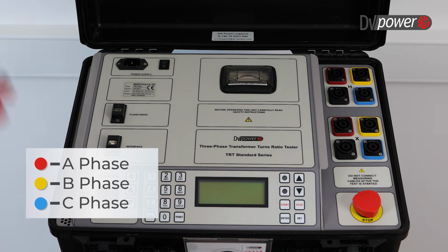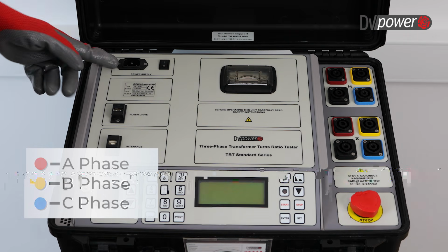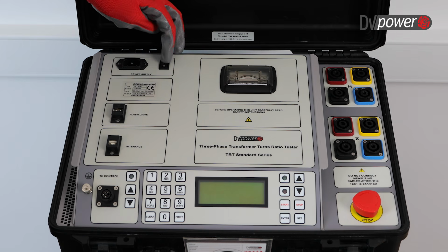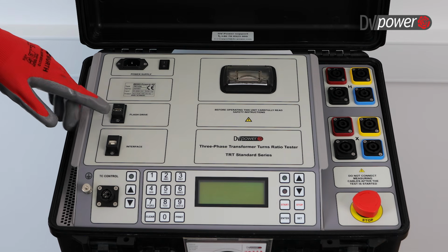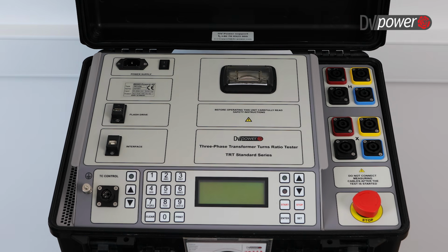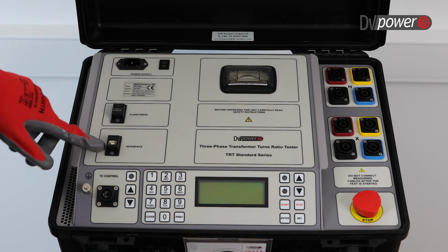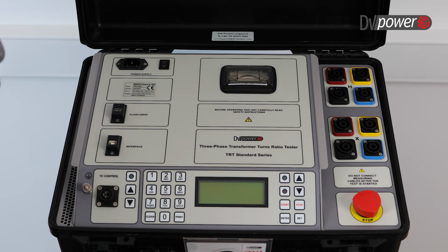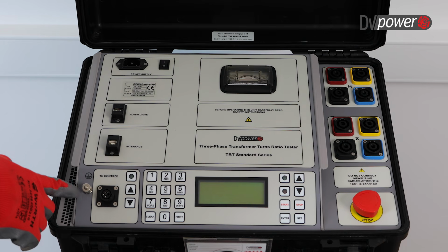On the left hand side, the power supply cable should be connected, and close to that there is a switch button. The flash drive port enables the user to insert a USB drive and download the data recorded previously by the instrument. The interface port enables the user to control the device from a PC and our DVTR software. The ground cable should be connected to this point.